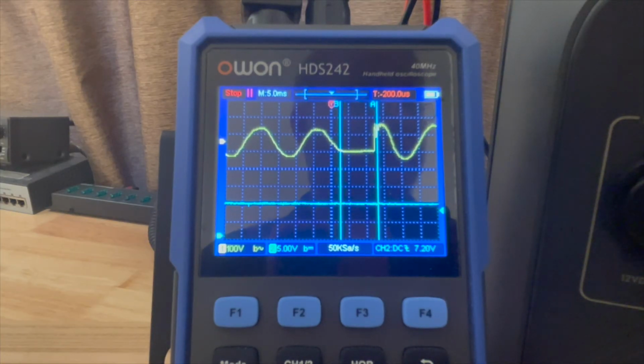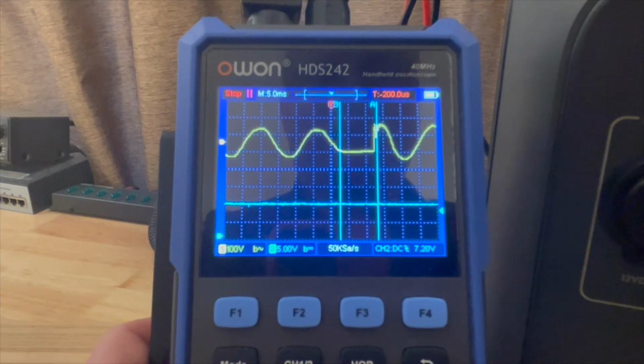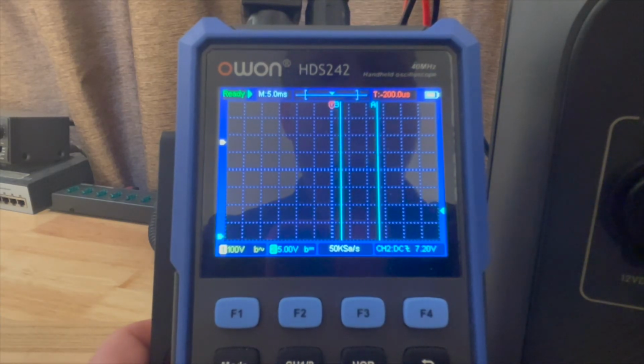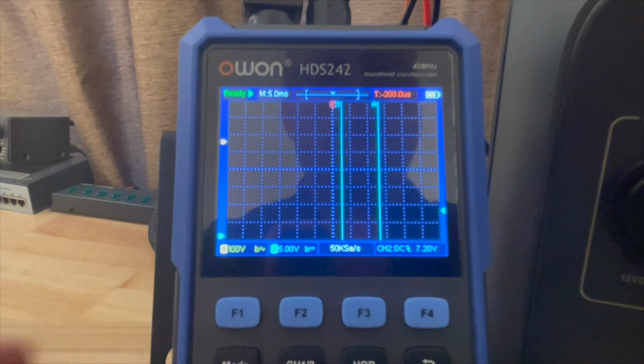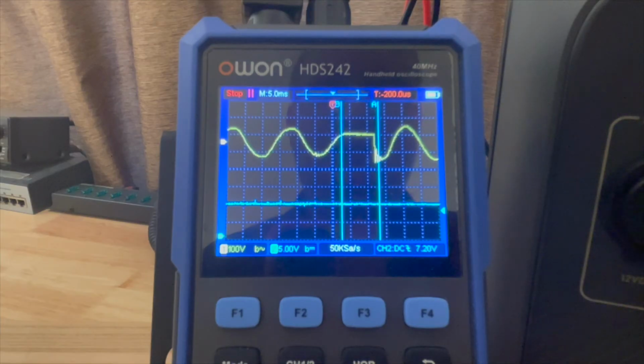But if I turn the power back off, set it back to grid power again, and reset the test, I'll probably get a slightly different value, because it really depends on exactly where in the sine wave the power cuts off. Let me cut it off again - see, this time I got a slightly longer time, but it's still in the 10s, definitely not up in the 20s. So we're in the 10 millisecond-ish range. Let me do one more just to make sure.